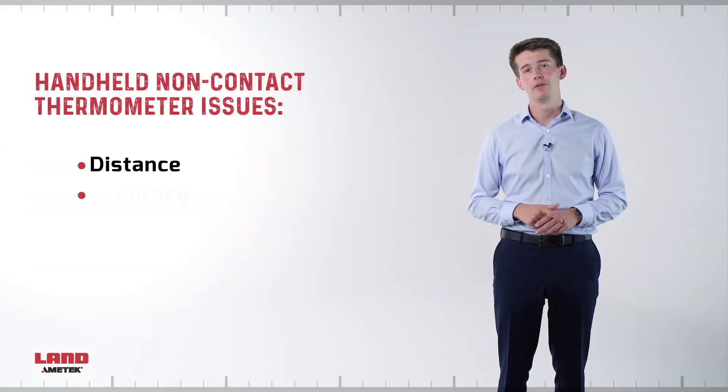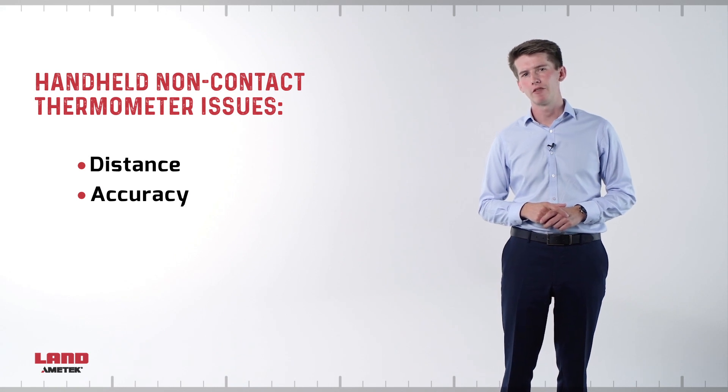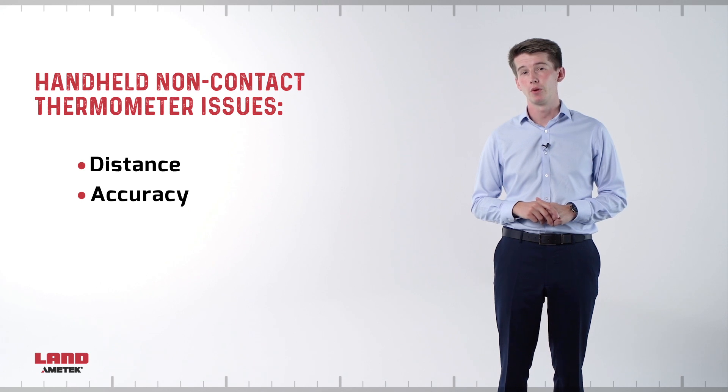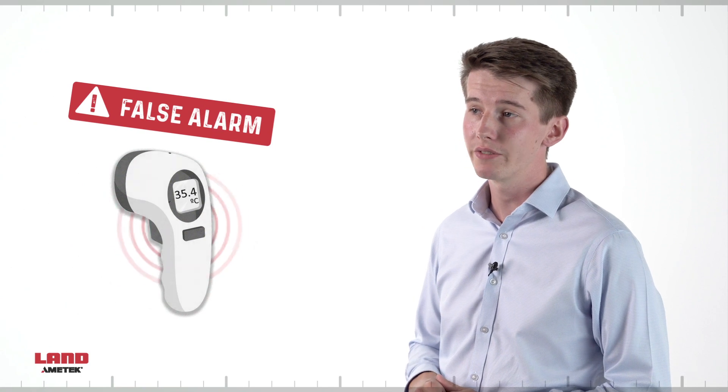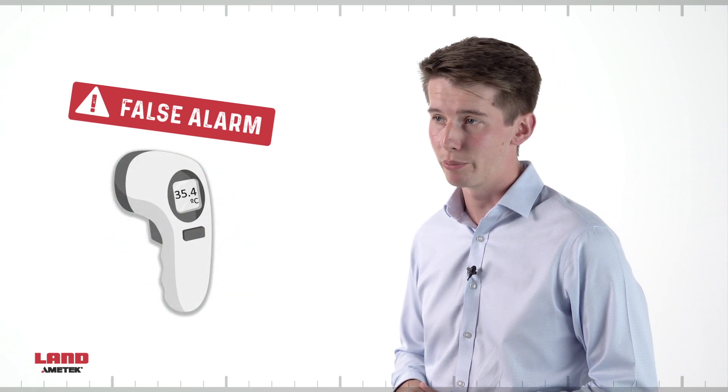The second issue is accuracy. Portable infrared thermometers often have a measurement uncertainty around 2 degrees Celsius or 3.6 degrees Fahrenheit. This is likely to create a lot of false positives and negative readings when you are trying to detect elevated skin temperatures.